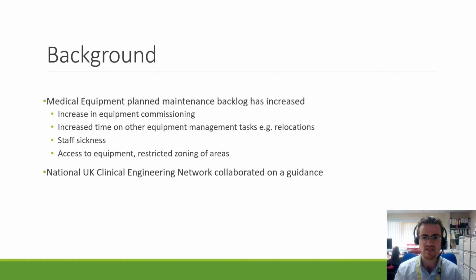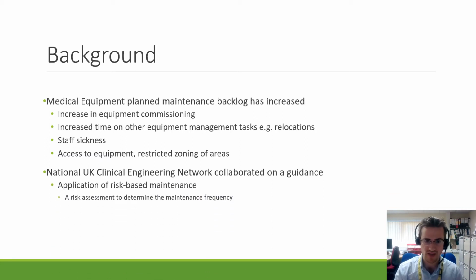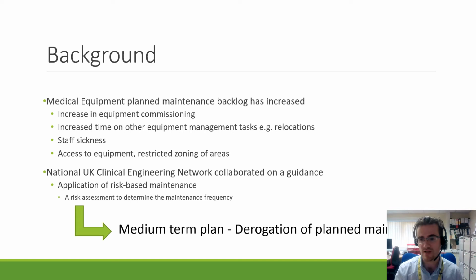So the UK Clinical Engineering Network came together to create a guidance document to address the backlog. One of the key parts was their application of risk-based maintenance, which is, to simplify it, a risk assessment to determine the maintenance frequency, and as part of one of their medium-term plans, so 6 to 24 months, they suggested the derogation of planned maintenance using risk-based maintenance. So that's effectively a delay in the frequency, a one-off delay.